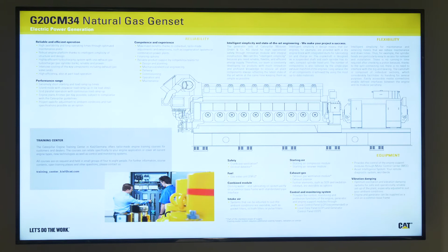I'm not going to dig too deep into the technical issues of the engine. The big thing is what you guys would call the heat rate or energy consumption - that engine is at 7,100 BTUs per kilowatt hour, pretty low fuel consumption. The overall generator set weighs 360,000 pounds, and unlike the high-speed product where you'd service it 4 times a year with oil changes and cost of ownership of oil, this engine holds about 1,000 gallons of oil and has a separate module and centrifuge oil cleaning system. So you never change the oil in the engine, you just add oil.